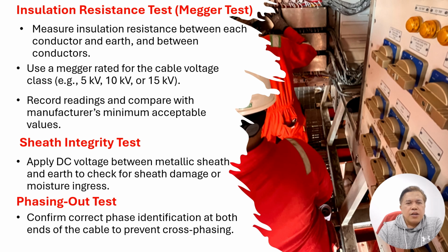So the phasing out test confirms correct phase identification at both ends of the cable to prevent cross phasing. It happens sometimes in the distribution board and sometimes in the switchgear. Phasing identification, like when you have a bus bar with vertical and horizontal bus bar connections, sometimes there's a mismatch in installation. For example, your vertical is R, Y, B and neutral, and your horizontal also has R, Y, B, neutral, but the R along the vertical is matched to Y on the horizontal. So sometimes there's a mistake, but it happens sometimes during the FAT.